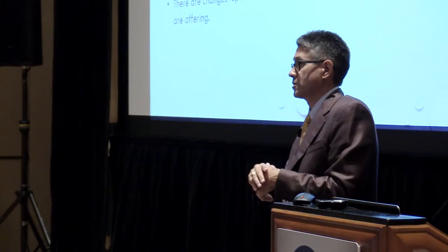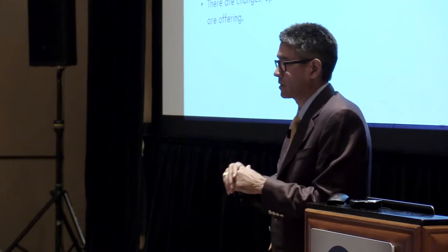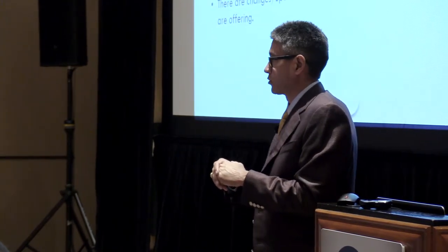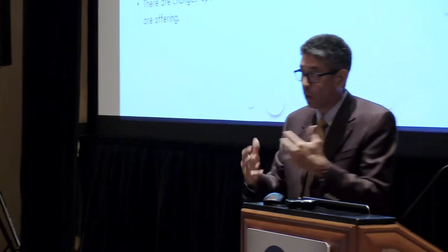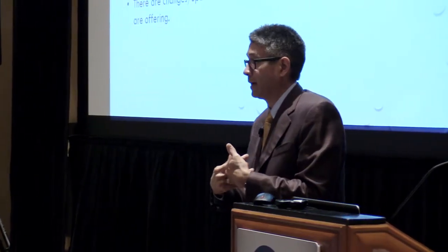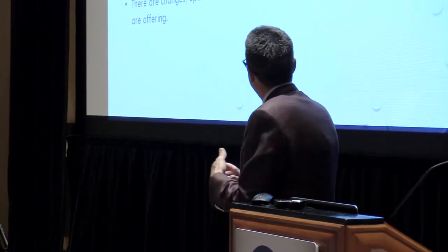We've had several systems where we've actually had them take them out and put in a normal control valve so we can get design water flow at the coil. So they're working on that side of it, I hear, but right now that's one of their biggest downfalls.